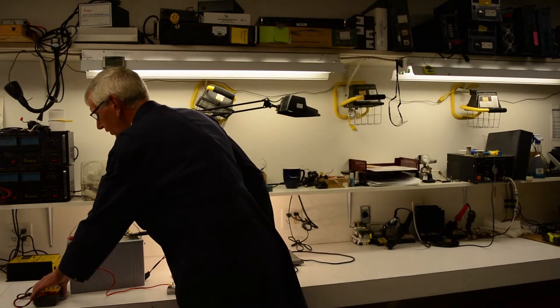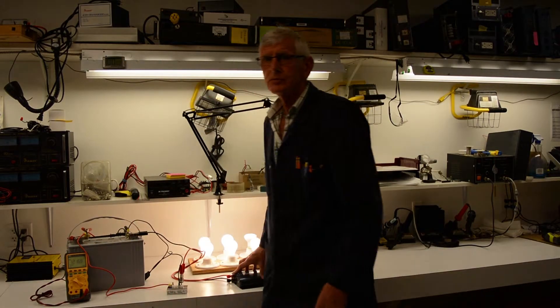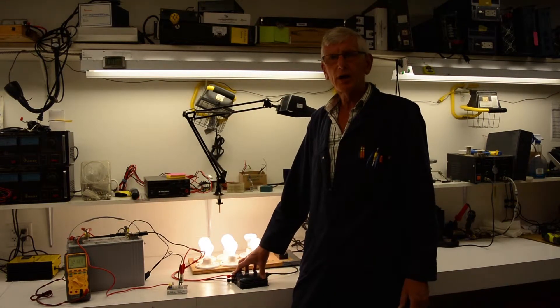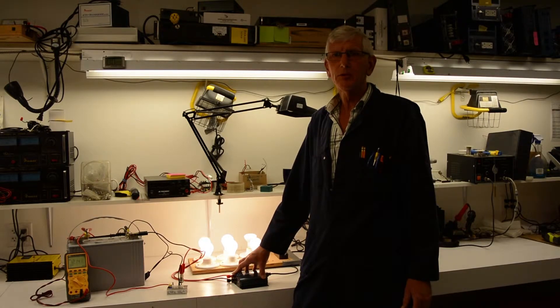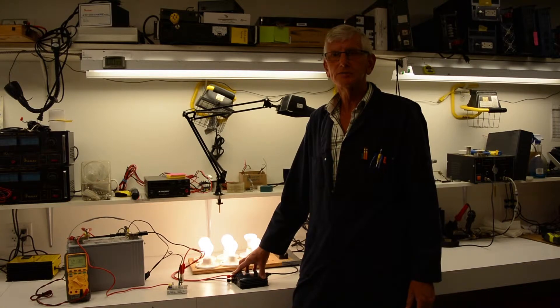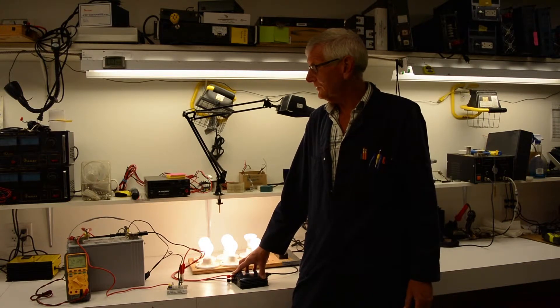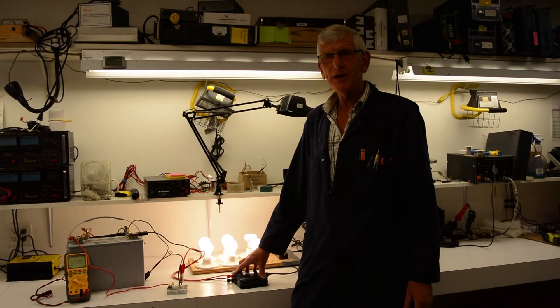So as the voltage drops, and when the voltage reaches the threshold that we have programmed, for 90 seconds, the unit will shut off the connection and wait for the voltage to be restored to about 13 volts with an external charger before it restores the connection. So we'll wait for it to cut it off. Be a couple minutes. Standby.